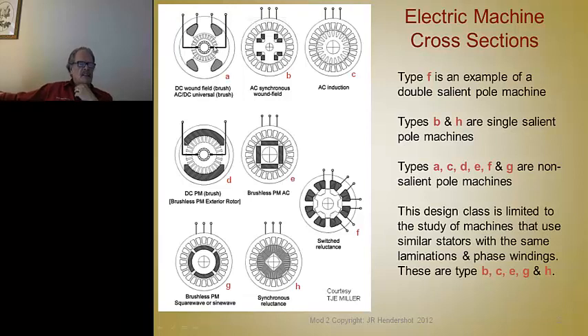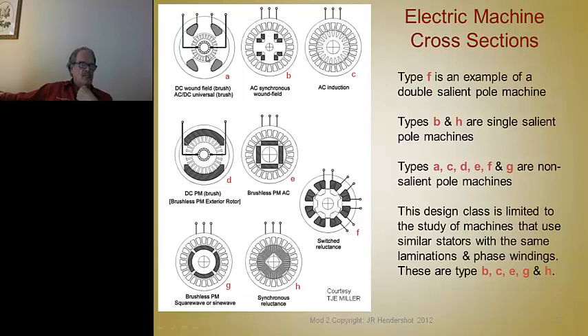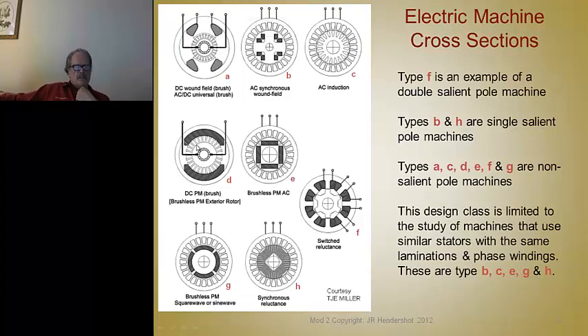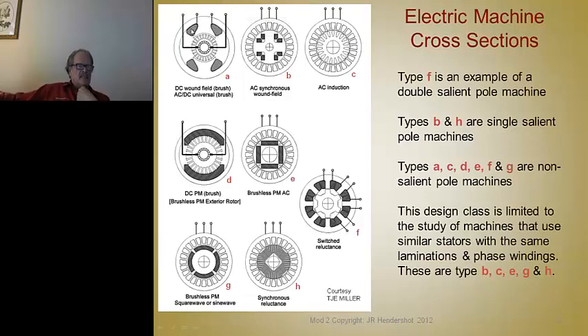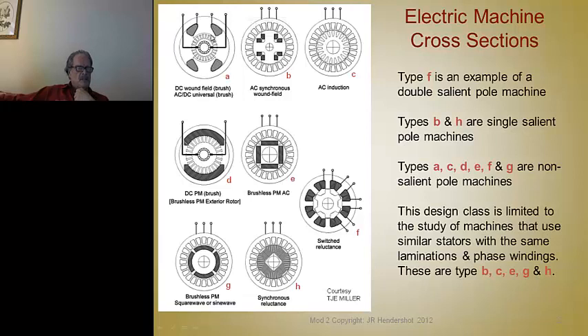If you reverse the polarity of the voltage across the terminals, you change the polarity of the flux generated by either the stator or the rotor. With permanent magnets in the stator, you just change the polarity of the armature. On a permanent magnet version, the flux from the permanent magnet is fixed — unlike the wound electromagnet, where you can connect a DC power supply, vary the field strength, and vary the torque-speed characteristics. The permanent magnet machine lacks that flexibility; its magnetic field is not adjustable.